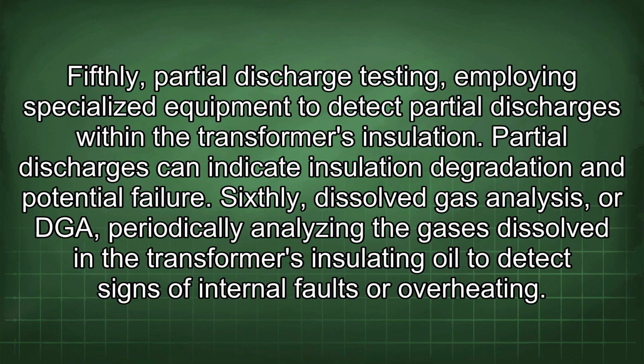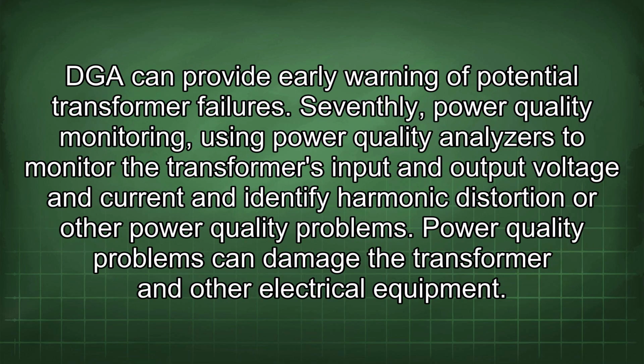Fifthly, partial discharge testing, employing specialized equipment to detect partial discharges within the transformer's insulation. Partial discharges can indicate insulation degradation and potential failure. Sixthly, dissolved gas analysis, or DGA, periodically analyzing the gases dissolved in the transformer's insulating oil to detect signs of internal faults or overheating. DGA can provide early warning of potential transformer failures.